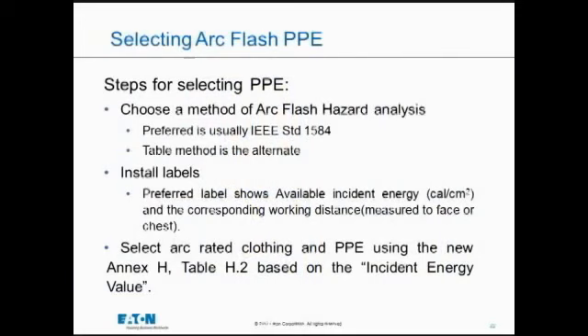So the steps boil down to decide, do you want to do detailed analysis or use the table method? Once you do that, you select one or the other, do your analysis, put labels on the equipment, and from the labels you select your personal protective equipment. If you're using the table method, you can use the HRC, hazard risk categories. If you use detailed analysis, then you must go to a new table in the best practice guide. It's called Annex H. It's at the very bottom of this slide. There's a brand new table as of January this year that is supposed to be used for arc flash hazard analysis calculations. And on the next few pages, I guess I got one more to go here.